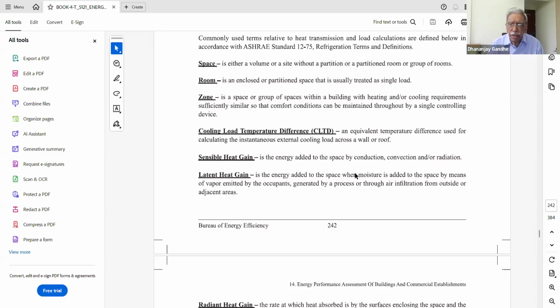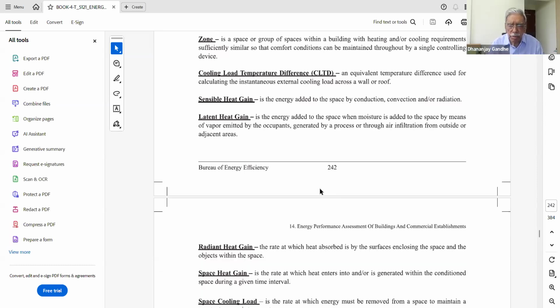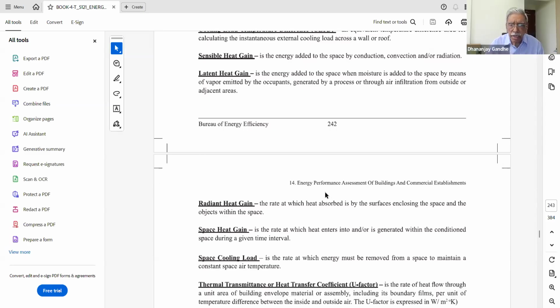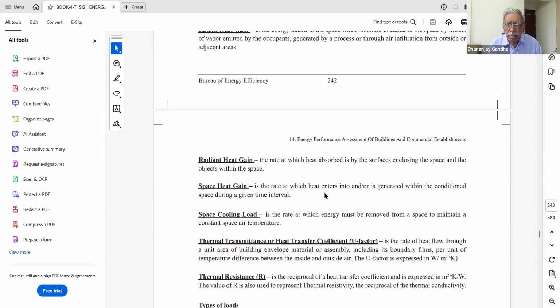Then maybe infiltration of air from outside. So some of these sources are given over here. Then there is radiant heat, which is the heat that is radiated within the space from outside. Space heat gain is the rate at which heat enters from various sources in a given time interval. Space cooling load is the total load inside, which constitutes the load on the air conditioning system, which generates heat and constitutes load in the system.